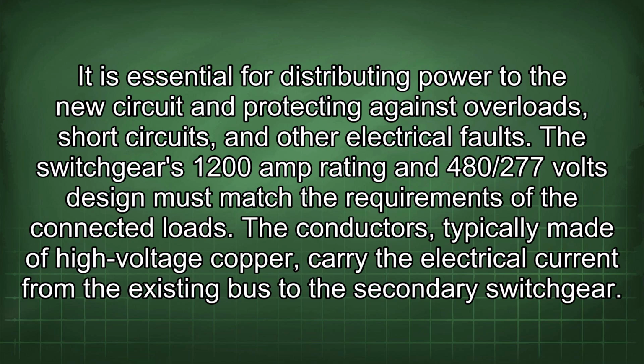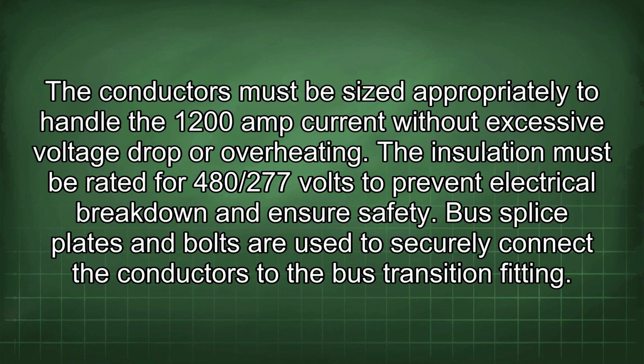The conductors, typically made of high voltage copper, carry the electrical current from the existing bus to the secondary switchgear. The conductors must be sized appropriately to handle the 1200 amp current without excessive voltage drop or overheating. The insulation must be rated for 480/277 volts to prevent electrical breakdown and ensure safety.